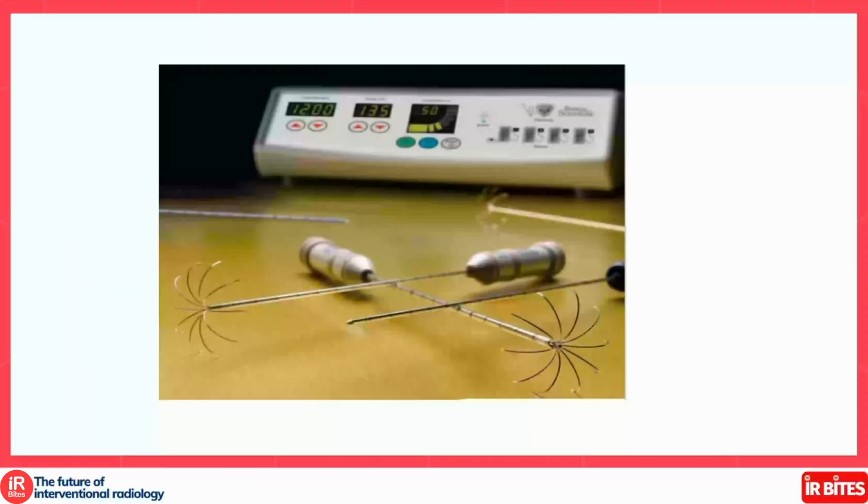This is an image of a Boston Scientific LeVeen system. I don't know if you can see my cursor on the screen. This is the box where you connect the grounding pads, and you set the energy on here. That's the wattage, and the time on here. So you typically start at about 50 watts, increasing 10 watts every 10 seconds up to about 90 watts. And then you'll wait for about 5 minutes from the start of treatment.